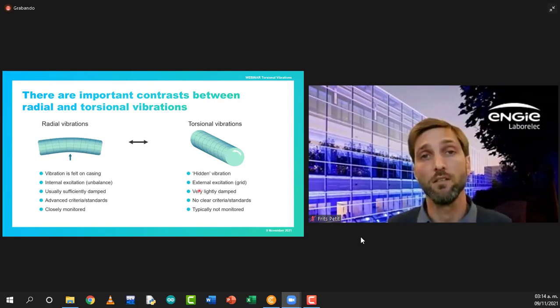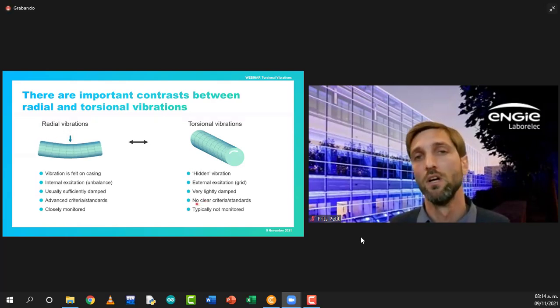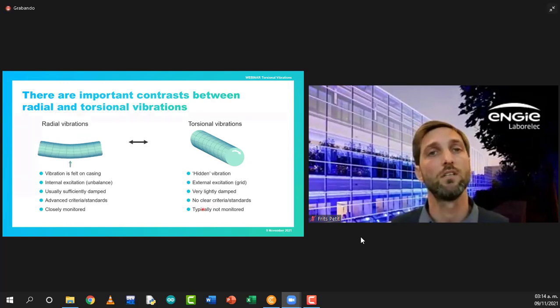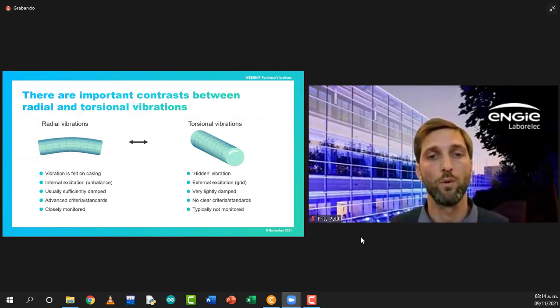They're very lightly damped because they're in the same direction as the rotation. So you want them to be lightly damped in that direction. Criteria and standards are not well advanced, and typically they're not monitored. It's not a standard part of your monitoring equipment.